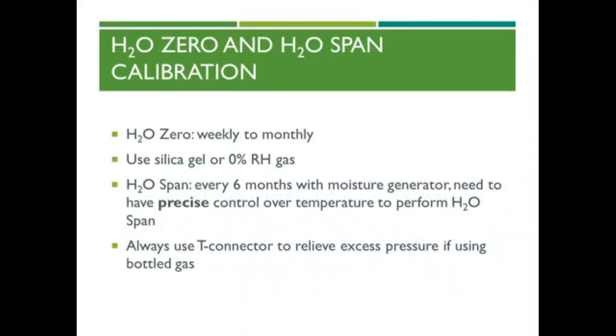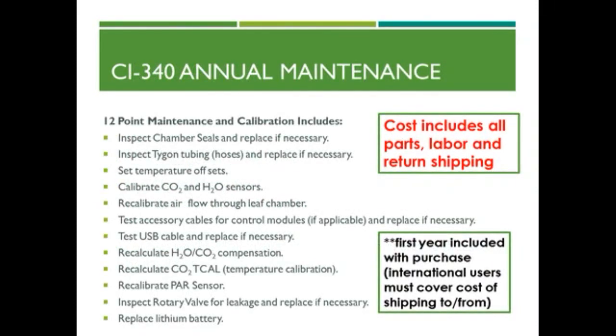The water sensor should be zero calibrated weekly, or if not frequently used, monthly. Use a desiccant, like silica gel or 0% relative humidity gas, to zero calibrate. Silica gel is provided with the CI-340 to perform this calibration. Always allow the silica gel to run for at least 10 minutes before determining if zero calibration is necessary. Like the CO2 sensor, span calibration should take place every 6 months to maintain the accuracy of measurements. Upon purchase of the CI-340, a 1-year warranty is established and includes a 12-point maintenance and calibration of the unit.